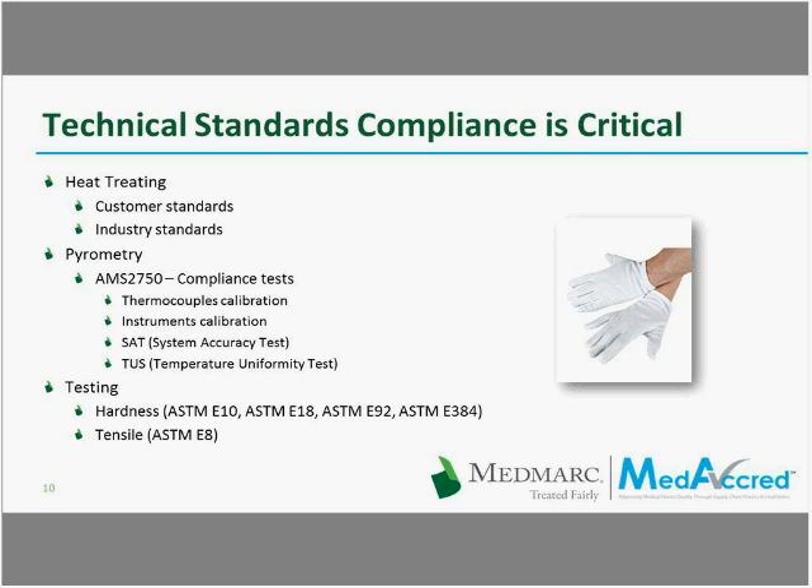For the critical process of heat treating, we can focus on three types of standards: the proper heat treating standards for each alloy, a pyrometry standard to control the equipment, and testing standards. For pyrometry, MedAccred decided to adopt AMS 2750 — a standard borrowed from the aerospace industry and considered one of the most complex pyrometry standards in the industry. It implies four types of compliance tests: tests that apply to thermocouples, tests that apply to instruments, system accuracy tests, and temperature uniformity tests.